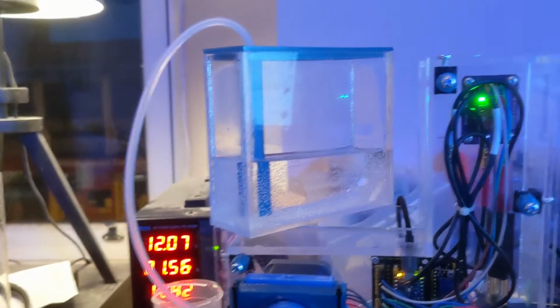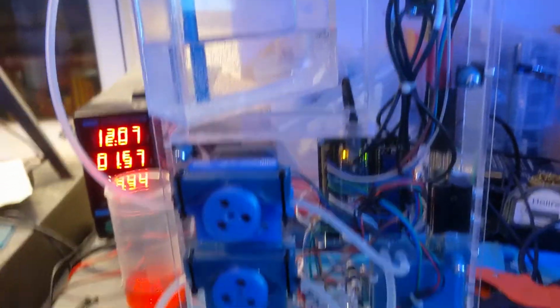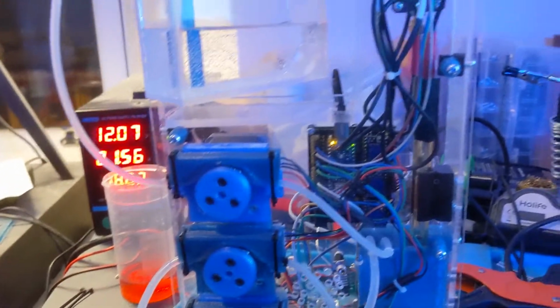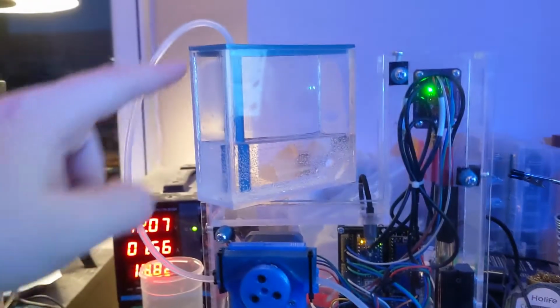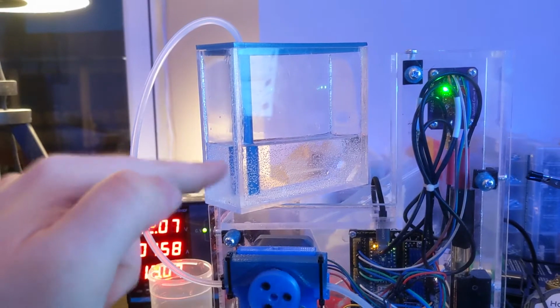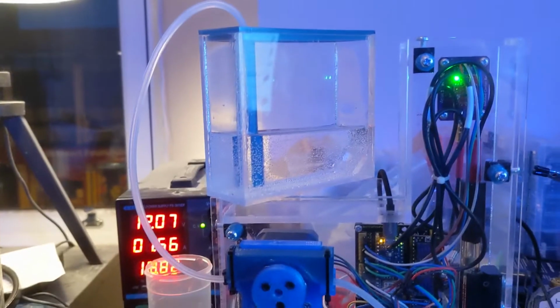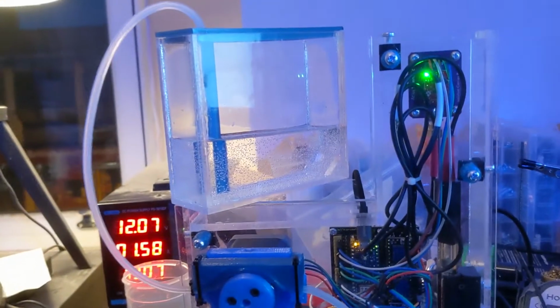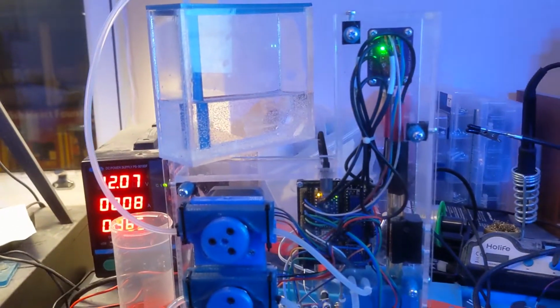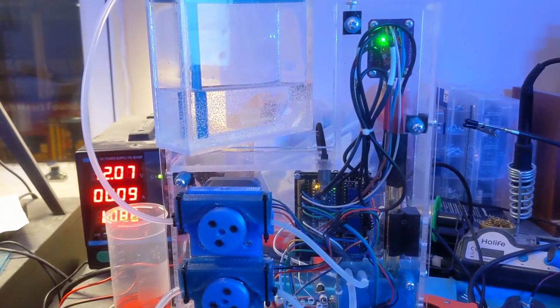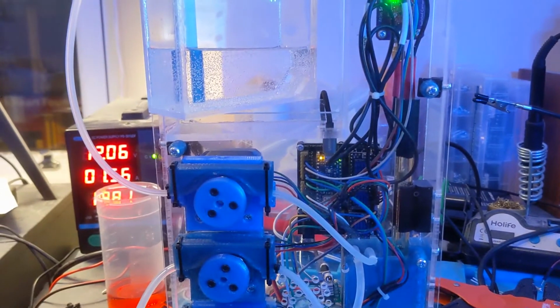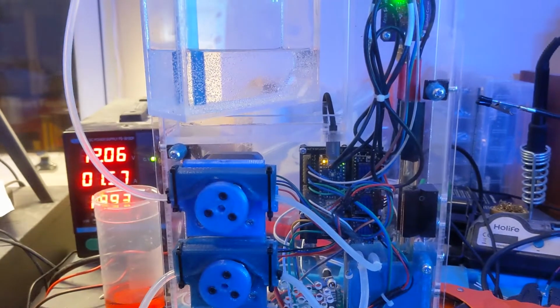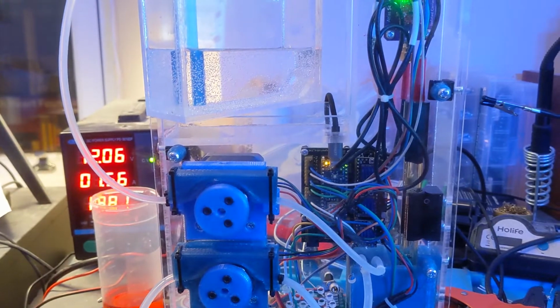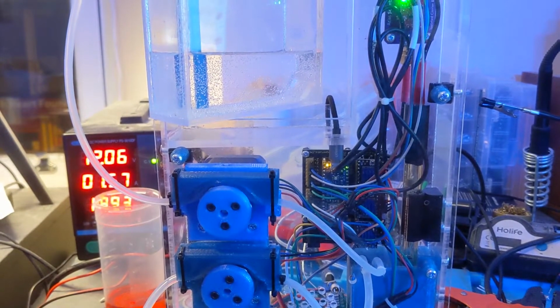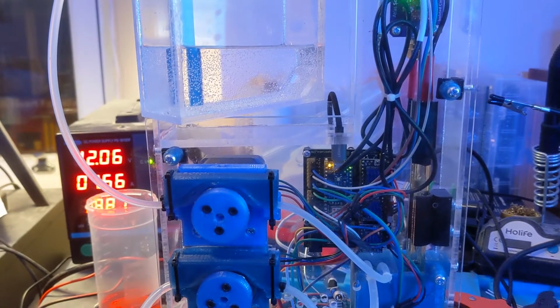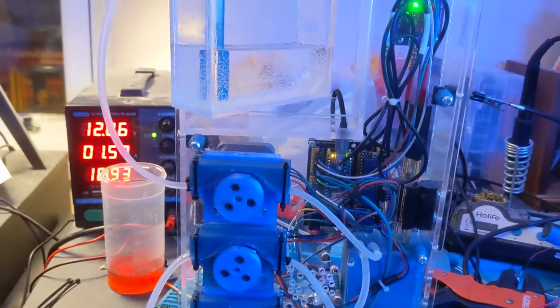So if you go to higher concentrations, you'll use less per test, and you can leave it alone for longer without refilling it, but the accuracy will suffer. So at 0.02, this holds enough to run somewhere around 70 or 80 tests. So I'm going to have mine set up to test every 2 days, which means I can leave it for 2 or 3 months without even checking the levels on the reagent. So we've reached a pH of 5.95 now after adding, looks like, 2 milliliters of the reagent.